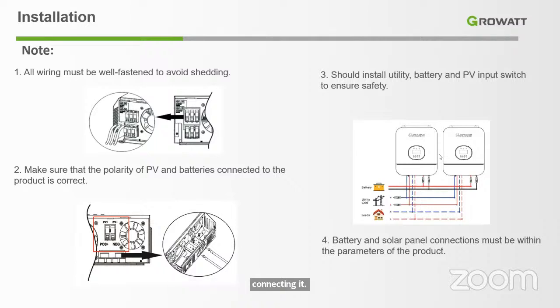As Julian said before, it's very important when you're going to parallel these systems. Someone was asking in the chat about three phase, or paralleling for one phase but with more power. There is only one battery bank for the whole system -- it's not like you can put one battery bank for one inverter and another battery bank for the other inverter. It's not going to work like that; you'll get a warning or error message from the LCD or the monitoring system.